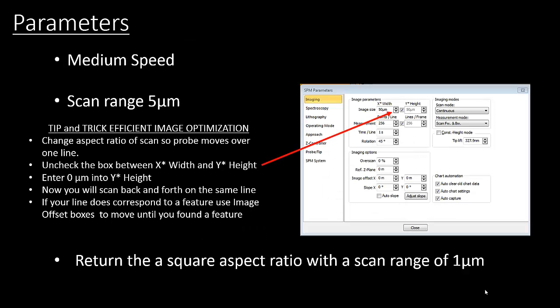The parameters for this experiment are as follows. You will first scan at medium speed with a scan range of about 5 microns and then optimize the image. Here, we have a quick and efficient tip for image optimization. You will change the aspect ratio of the scan so the probe moves over only one line. To do this, we need to go to the SPM parameters window. Here, you'll uncheck the box between X star and Y star. In the Y star box, you'll enter 0 microns. Now you'll move over only one line.